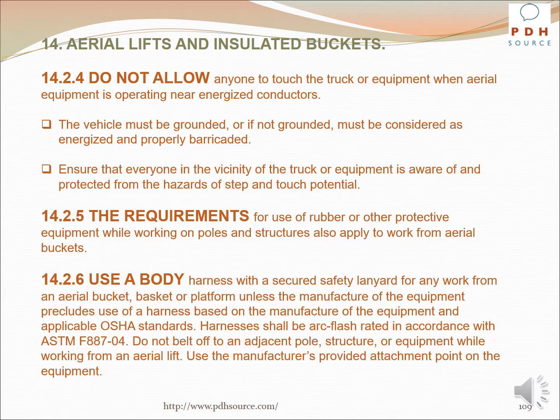Use a body harness with a secured safety lanyard for any work from an aerial bucket, basket, or platform, unless the manufacturer of the equipment precludes use of a harness based on the manufacturer of the equipment and applicable OSHA standards. Harnesses shall be arc flash rated in accordance with ASTM F887-04. Do not belt off to an adjacent pole, structure, or equipment while working from an aerial lift. Use the manufacturer's provided attachment point on the equipment.